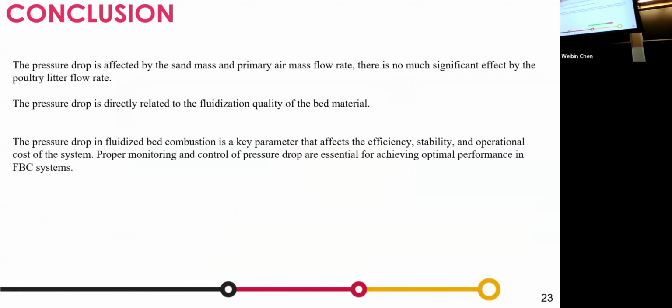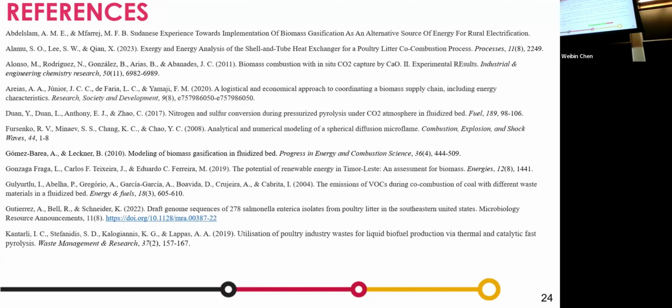So as a result of this research, we are able to find out that pressure drop is greatly affected by the sand mass and the primary air. There's no significant effect, even when you start increasing your poultry litter flow rate. It's better you maintain a steady one and ensure you have complete combustion. The pressure drop is directly related to the fluidization quality of the bed.